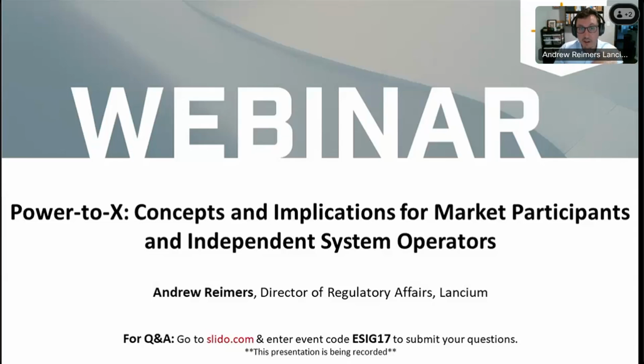As long as I'm following that instruction, somewhere else on the other side of the equation, load and demand and supply are in balance with each other. It's the out-of-sked ramping that's being balanced by regulation, and new signals are sent to whoever's providing the regulation every 4 seconds. But it's not uncommon for that regulation to be totally exhausted, so then there's no other units to turn up to balance supply and demand.